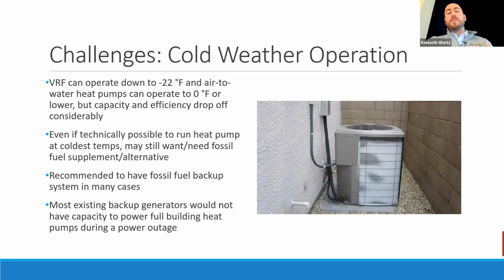So in many cases, as I mentioned, you want to keep that natural gas boiler or keep that oil boiler as a backup, run it intermittently to keep it fresh and available. And we talked about the increased energy costs associated with running heat pumps versus boilers. You may find that you have to switch over to the boiler when it's cold outside, even if the heat pump's capable of still running, just to avoid sending your electric bill through the roof. So that's a challenge: you're often going to have to keep two systems in parallel to be able to keep your building reliably warm throughout the whole winter.